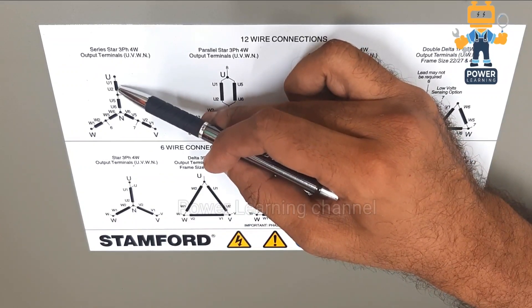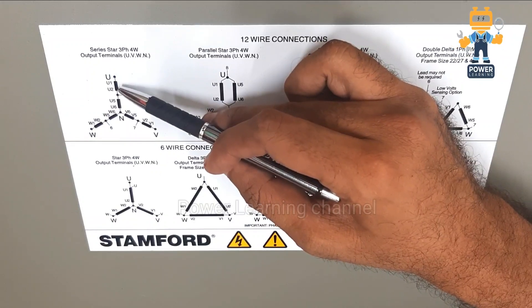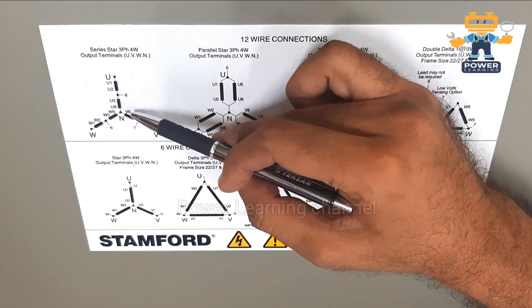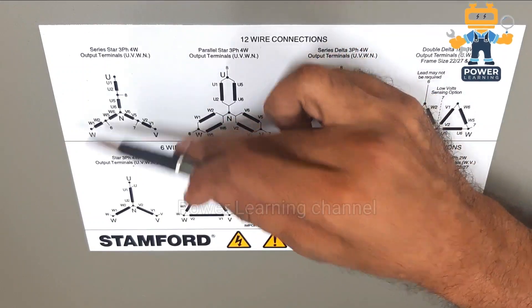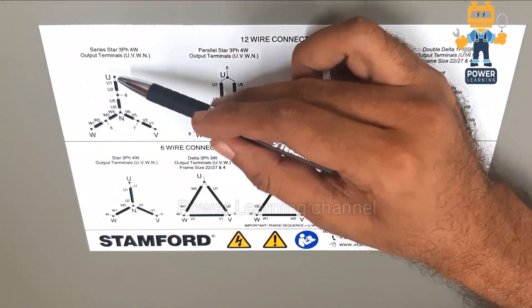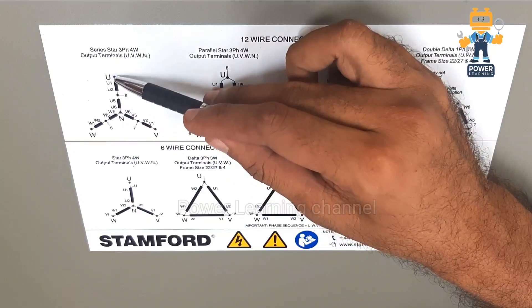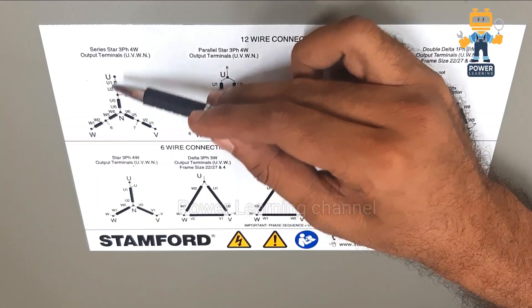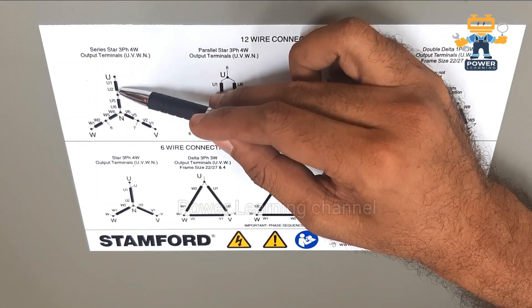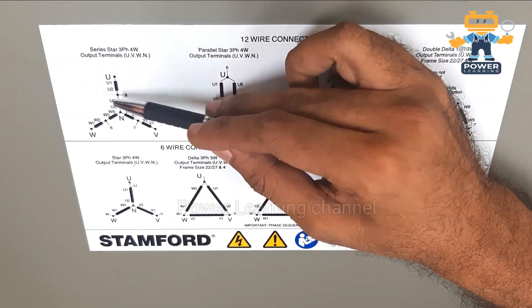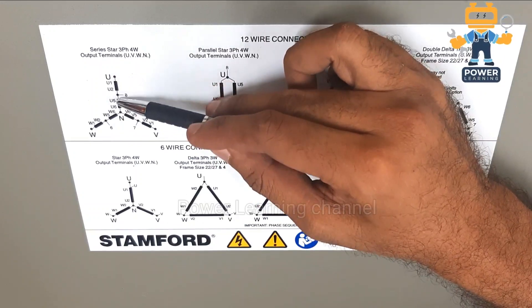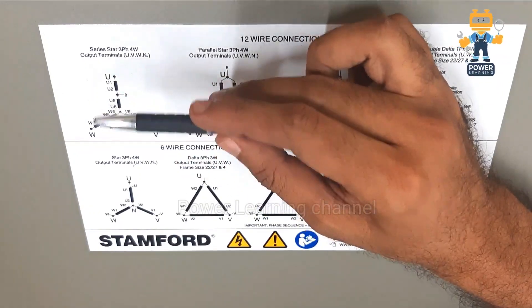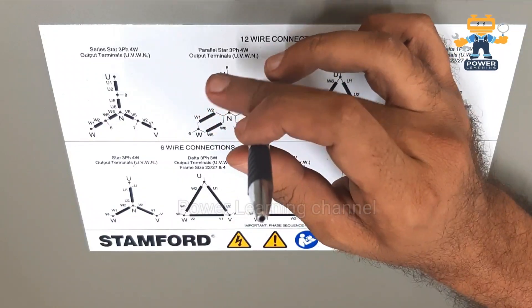We have one coil, two coils, three, four, five, and six — six coils total, each coil having two ends: a starting end and an ending end. Six multiplied by two gives a total of 12 leads, so that's why we call this a 12-wire connection.